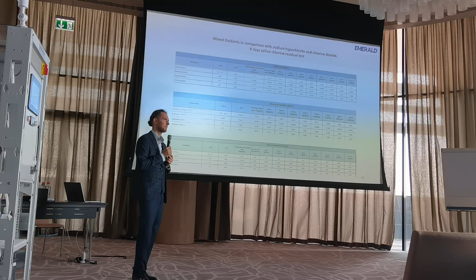This is the problem of traditional sodium hypochlorite generators. Exactly. Because when you just take the brine, bromide will be there. And when you are passing this brine through the anode and directly go to the water, you will add bromate to the water. In our case, we separate pure gas from the anode chamber. We do not inject brine into the water. From our brine in the anode chamber, we separate only gas and inject this gas to the water. That is why it's much more clean.